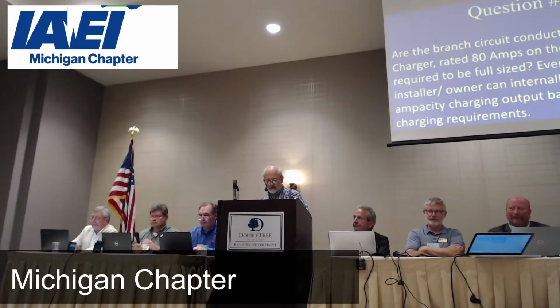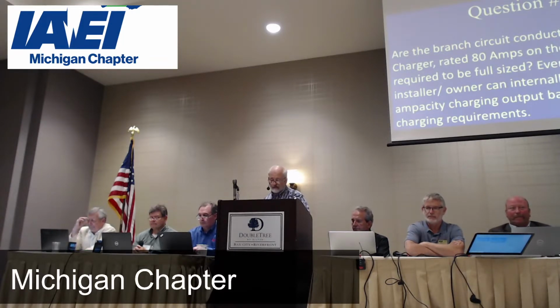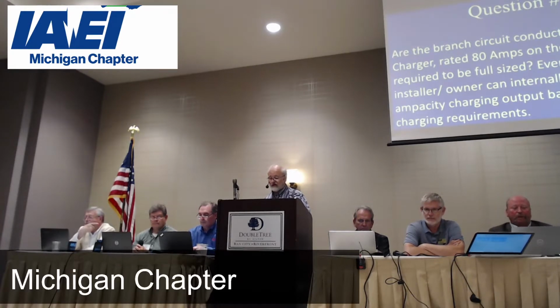Okay, let's see. Question 34, Kim. Are the branch circuit conductors feeding an EV charger rated at 80 amps on the nameplate required to be full size, even though the installer/owner can internally select a lesser ampacity charging output based on the vehicle charging equipment requirements? And so here's another example of where timely adoption of the NEC can actually pay off.